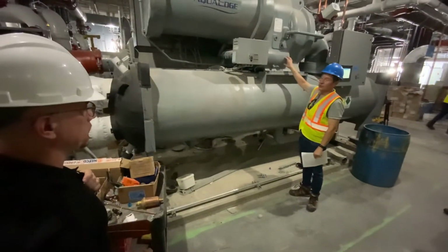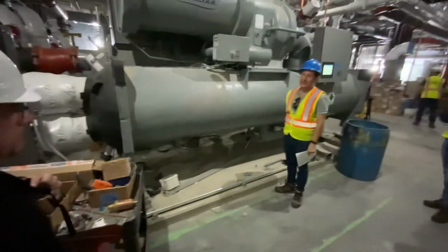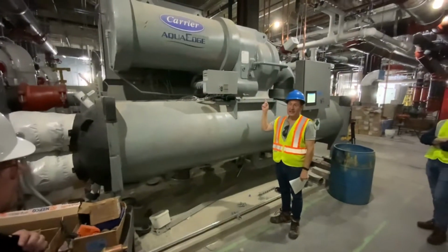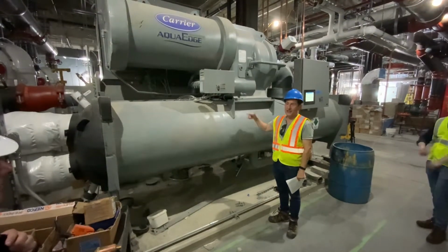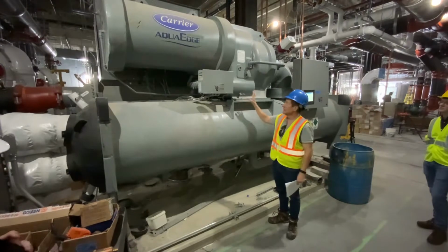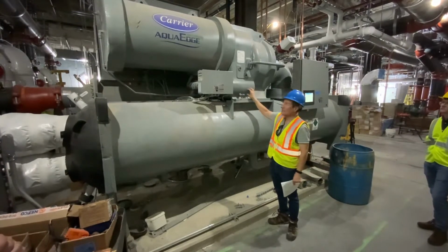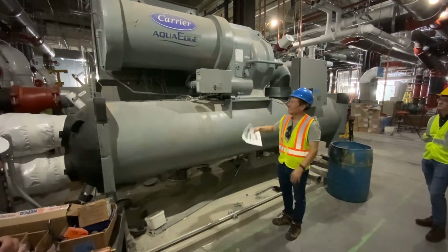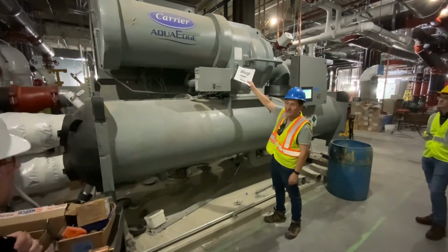Yep. Because when the chiller turns off, the oil heater turns on. I don't know if you can actually hear it. Periodically, when the chiller's off, the oil pump turns on to agitate the oil and make sure it mixes and gets the heat distributed. So that's in the oil basin below. The sight glasses, obviously you can't see them now where they're supposed to be, but this sight glass would be about half filled with refrigerant.